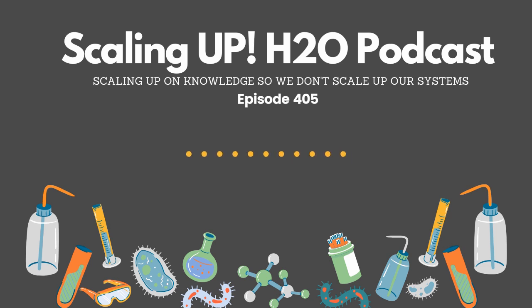So, as a former boiler inspector, I guess I got to pick a boiler. Let's say in a water tube boiler, what's one of the first places that you're going to find evidence that water treatment's not working? Well, usually we go in the steam drums, and you actually see any type of corrosion or scale formation in the tubes that you can see easily when you got it. And also when you see a really good treated boiler, you immediately notice a very well passivated surface. It's like you see in the books when you start learning and studying that. But yeah, I mean, just looking at corrosion and deposition and scales in the tubes.